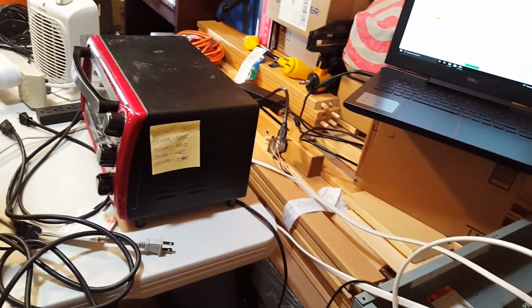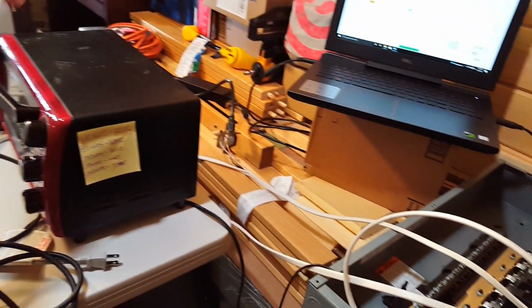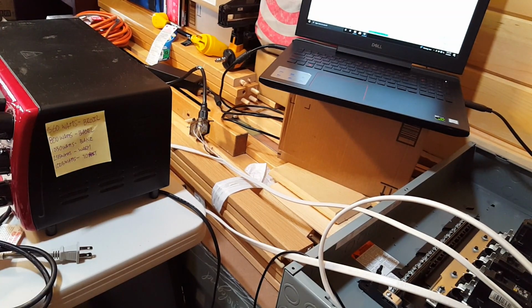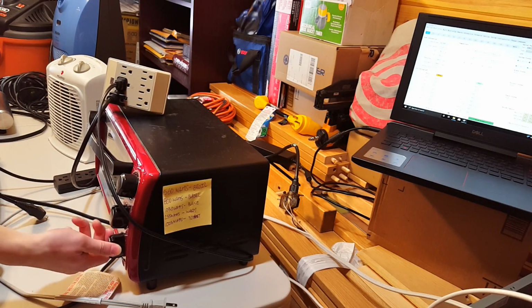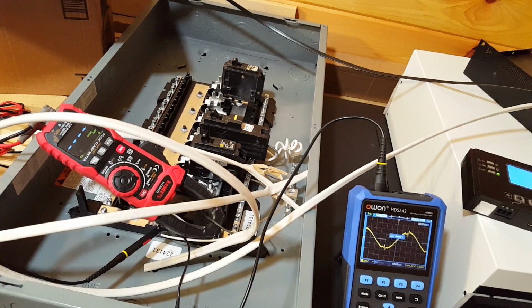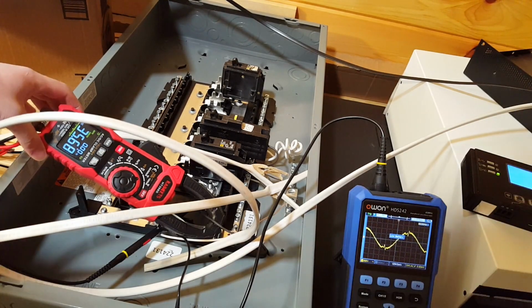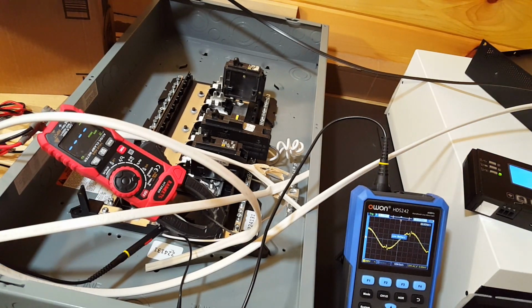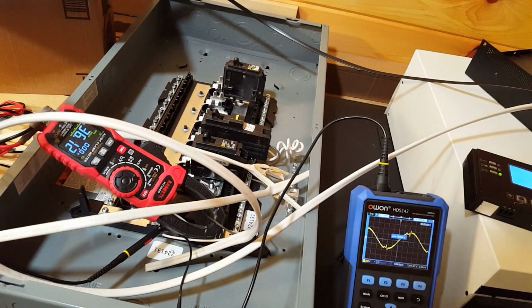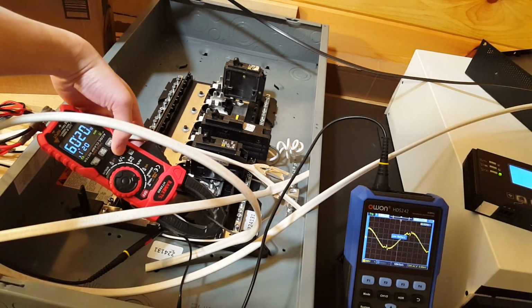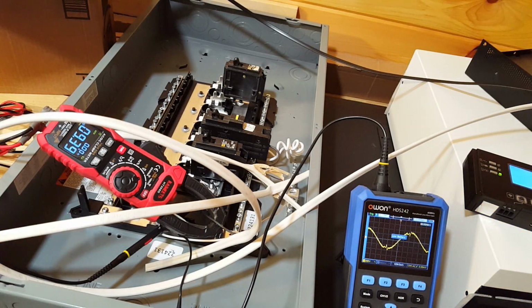Let's go back to the orange shop vac, which has a weaker surge, and we'll add a 1,000 watt toaster oven load, and then we'll add the motor. 1,000 watts on the toaster oven first. 23 amps discharging. Okay, I've got inrush mode testing. 1,000 watt load. Now we're gonna add shop vac. Will it start? No problem. Let's try again. What's that surge? 35.68. Second try. 36, the second try. Let's see what the AC running amps is in total. 9.4 amps going.